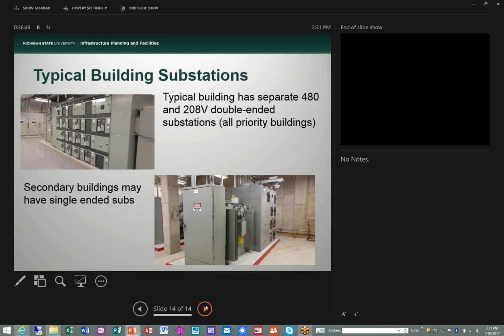So your cables are 500 throughout the entire length? It's primary. I think you're describing a primary selective, main-tie-main primary selective system. Are your cables the same length and size throughout? Yeah, for the most part. As I noted earlier, there are some offshoots that are 350s, and then the occasional one where we jump over and feed a single building. We've got a couple of locations where we've got 2 lots, but we've standardized on a cable, a custom spec cable, so to speak, an MSU standard cable through Kerite, and it's served us very well.